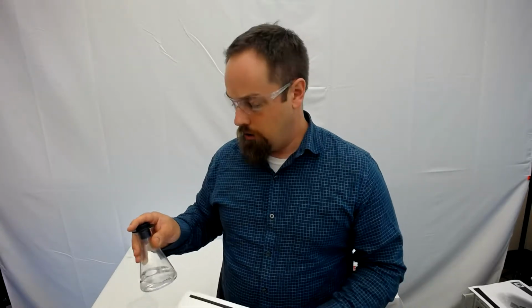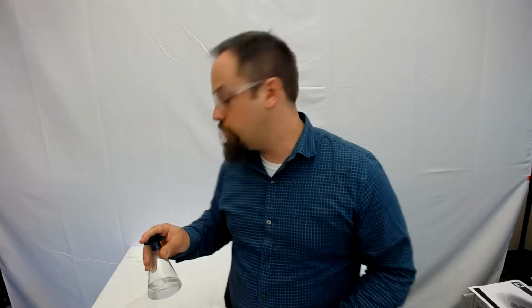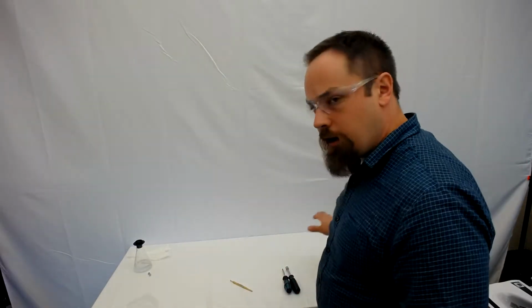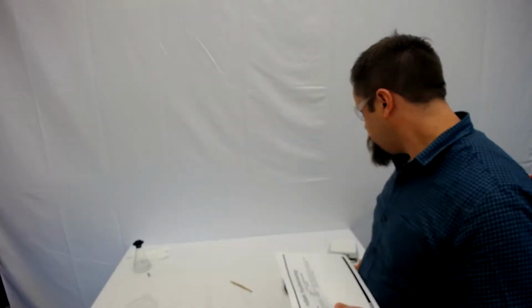Okay, so as we are troubleshooting, the main thing we're looking at is calibration if the unit will not reach the desired speed. So the unit is running either too fast or too slow. That could be because you have too high a volume of liquid or too viscous a liquid for the unit to push. It could be that a customer has the speed set at too low a speed and maybe needs to jump start it, like I just talked about. But if you're getting it back, it probably means that the user has gone through all these things, and the unit needs a calibration.